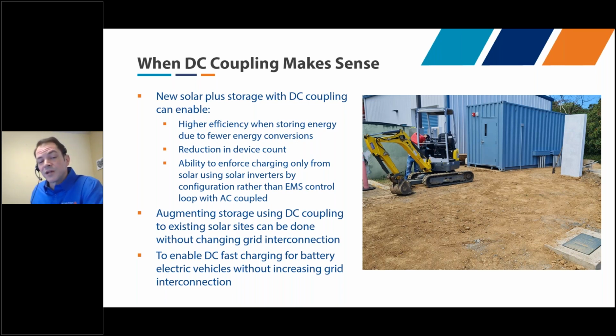Another advantage of DC coupled systems is you can do whatever you like on the DC bus without worrying about impacting the grid interconnection. Sometimes the grid interconnection can have complicated permits and so forth around it, so doing things on the DC side avoids the need to manage that. For example, you can add DC fast charging onto an existing DC coupled system without potentially increasing the grid interconnection. DC fast charging can have a significant impact on power draw from the grid, so it can be an advantage to do that on the DC coupling side.